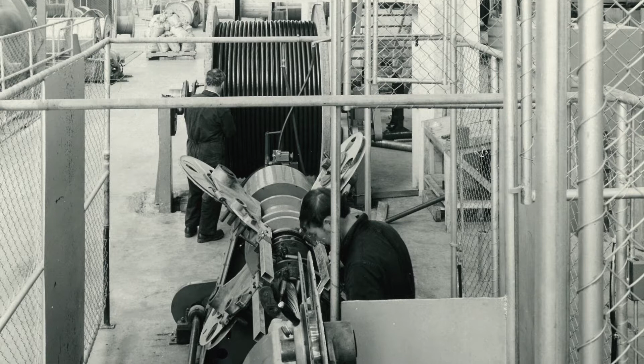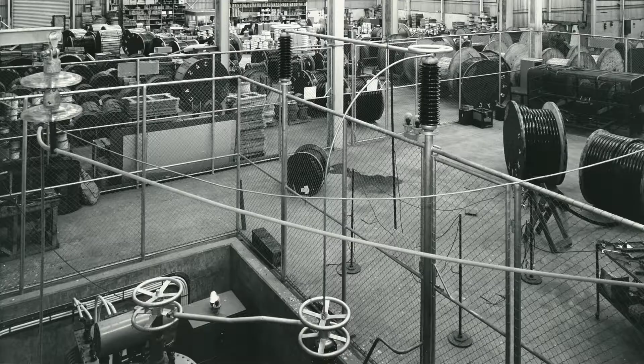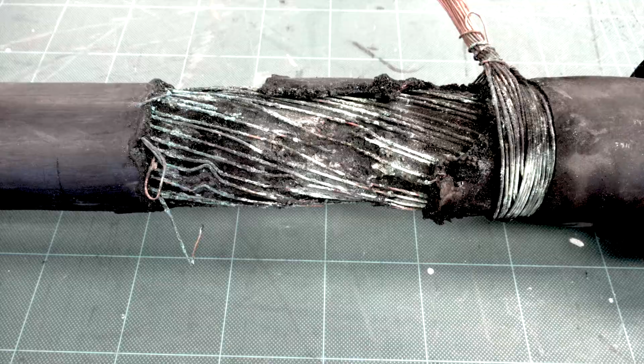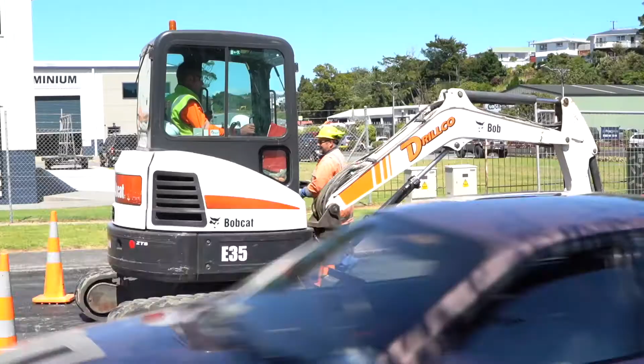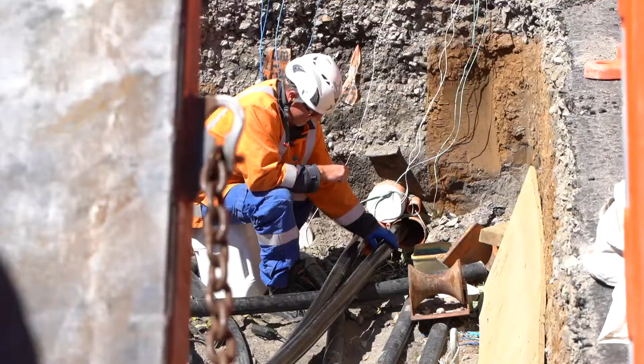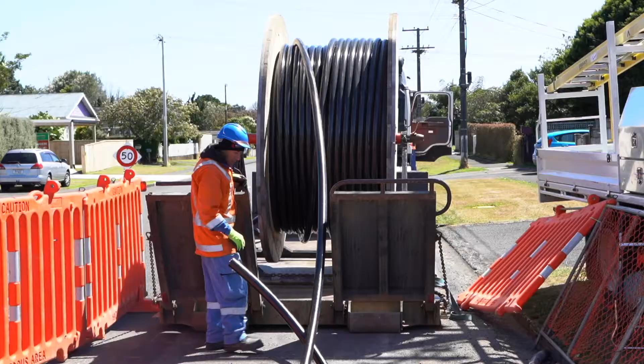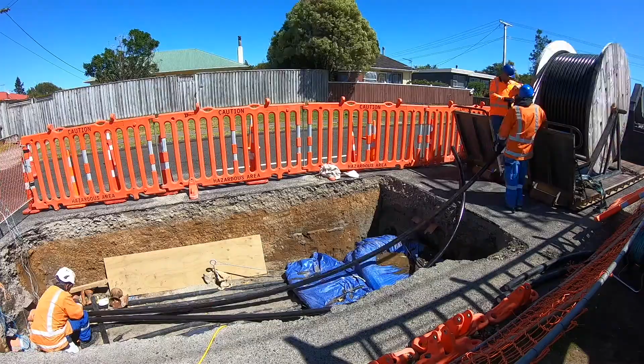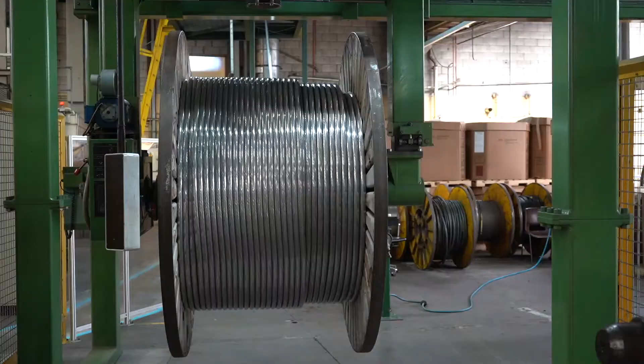Over 50 years ago, when the first medium voltage cross-linked polyethylene cables were installed, industry expected them to last for 20 to 30 years. However, multiple cases were recorded where cables failed after only 10 to 15 years. As a consequence, utilities began replacing what should have been a reliable, long-lasting product. It was estimated that for every dollar spent installing the cables, networks had to spend at least $10 to replace them. Some networks are still dealing with this problem today.